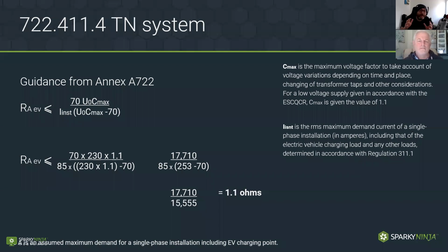And this value that we're calculating here is supposed to be the maximum value of RA of the electrode that we actually install to reduce that voltage in the area of the electric vehicle. And so you'll see a lot of people will go, it's just not practicable to achieve that low an RA. Most often, a single rod is most likely not going to achieve that. So people will start saying, well, you need to move on because the electrode method is just not very easy to achieve to get a guaranteed RA that's low enough in ohms.